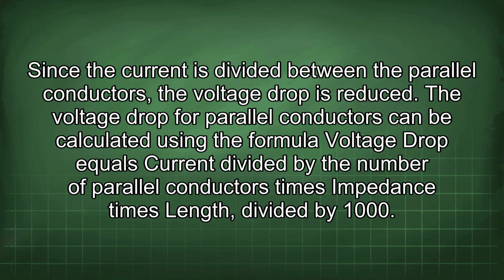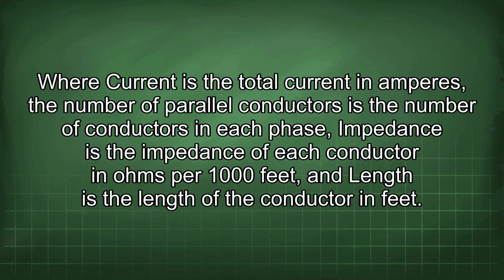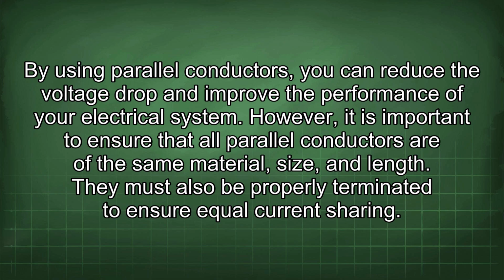The voltage drop for parallel conductors can be calculated using the formula voltage drop equals current divided by the number of parallel conductors times impedance times length divided by 1000. Where current is the total current in amperes, the number of parallel conductors is the number of conductors in each phase, impedance is the impedance of each conductor in ohms per 1000 feet, and length is the length of the conductor in feet.